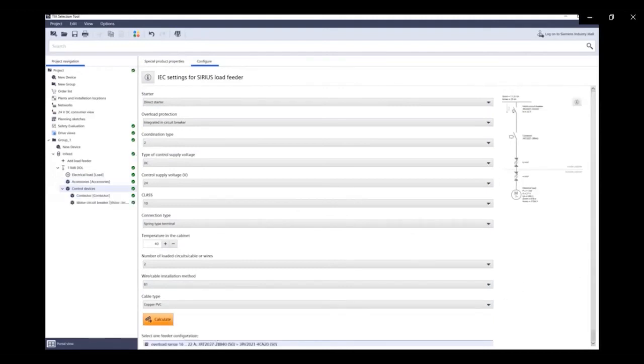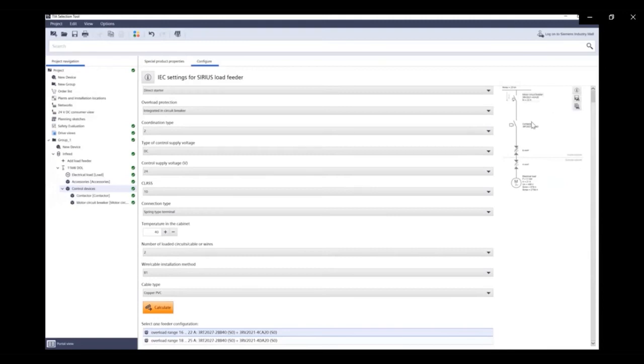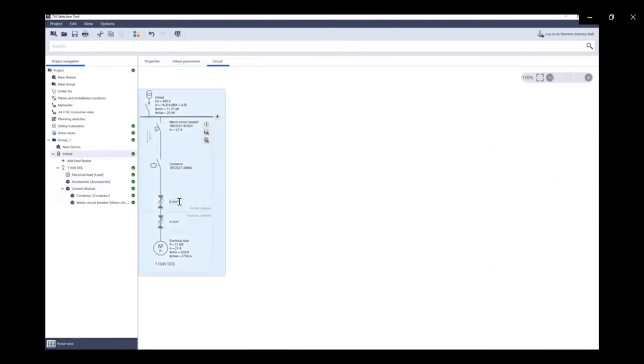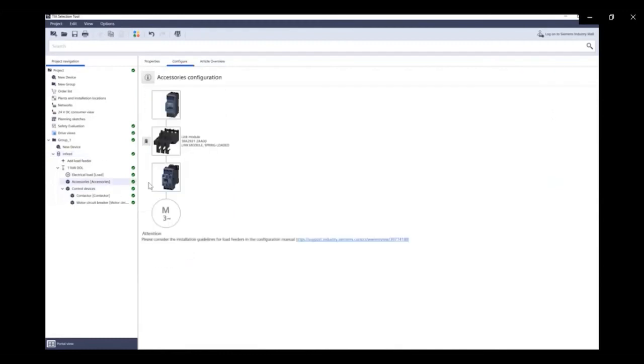and we see from the calculation that I receive different options on a protection device and contactors, which I can select to my demands now. So I selected the ones I needed. The wiring data is already calculated and visible here in the graphical view. And I can see the overall circuit for those here in my single line diagram. Accessories as shown here can be added, modified, changed as per your application requirements.